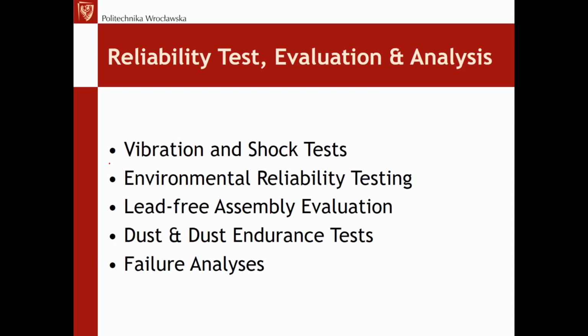From a practical point of view, there are plenty of tests that could be placed here, chemical even, and physical and chemical actually. Yet in my opinion, the most important here is first of all the vibration and shock test. Second of all, the environmental reliability test. In case of vibration and shock, it's about testing if everything is assembled properly, if everything is designed properly, because this is for R&D. In other words, if our device doesn't break up during normal operation, during day-to-day or everyday use.